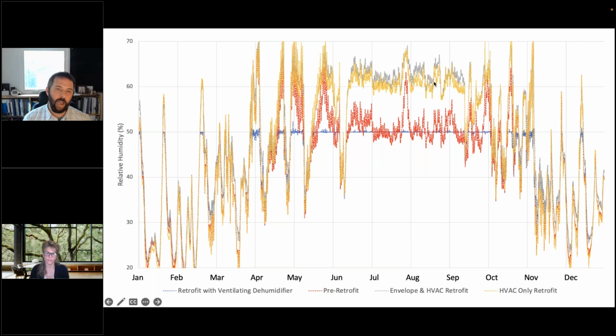So things to think about if you're going from here to here: is a client going to be happy if they paid about 50% out of pocket for this expensive retrofit, and you've left them with 60% RH in the dead of summer when before they were floating around 50%? I don't think it's going to be a happy client. My suggestion is that supplemental dehumidification should be part of the package, possibly as a ventilating dehumidifier, so the client can set the relative humidity where they want it and maintain it year round.